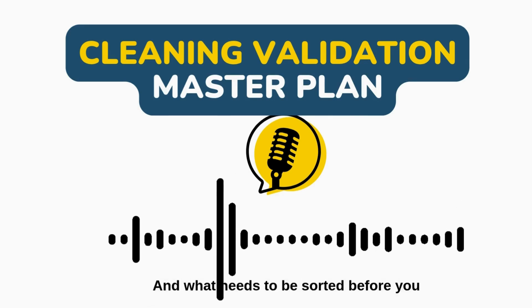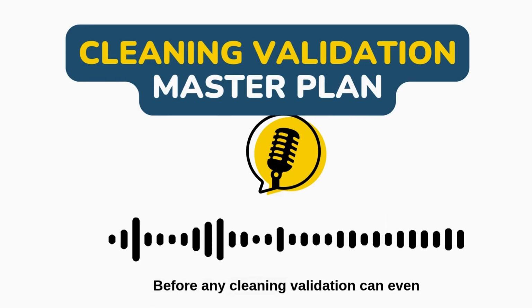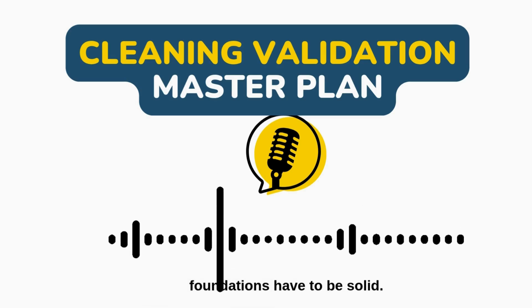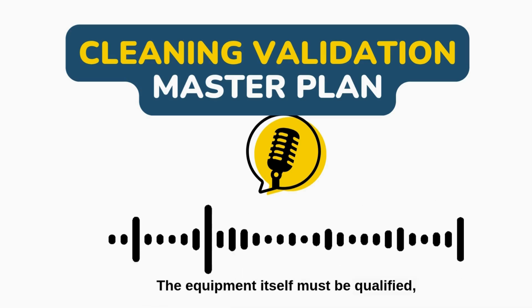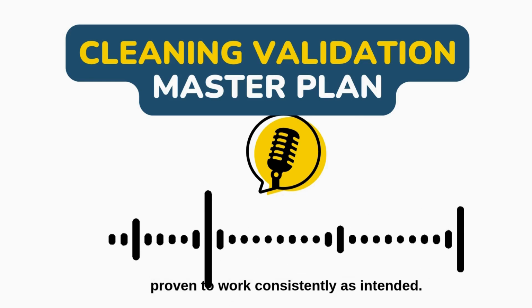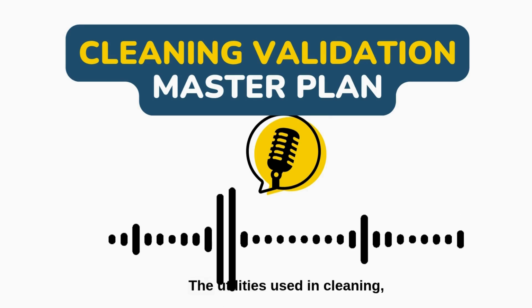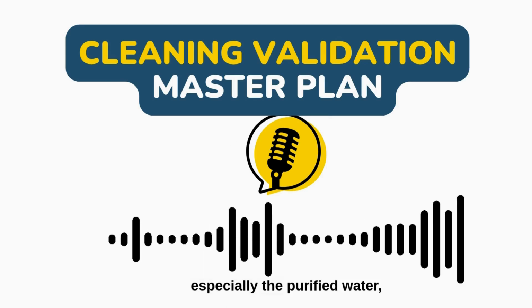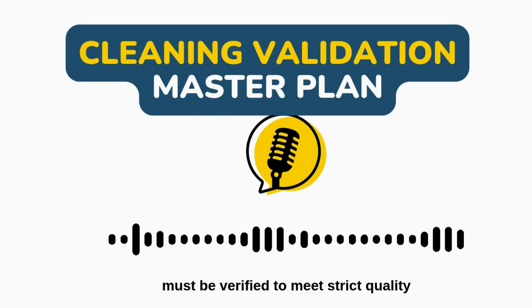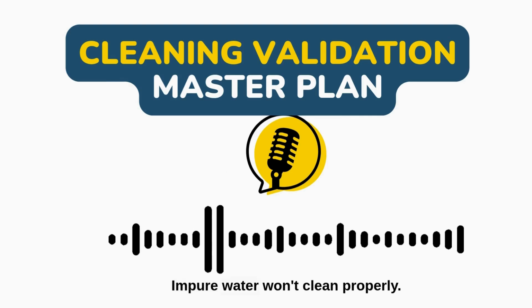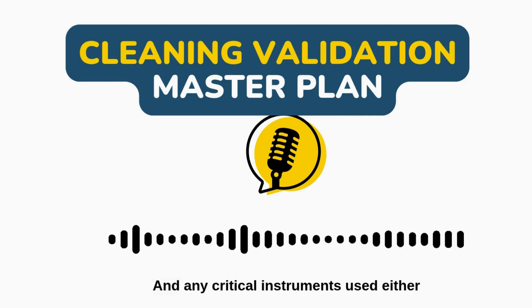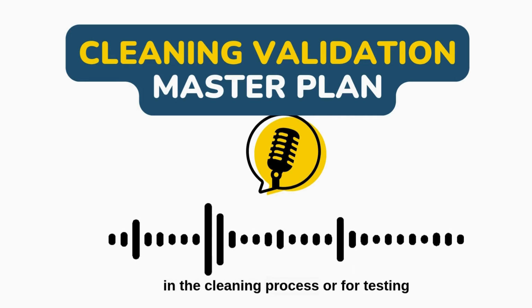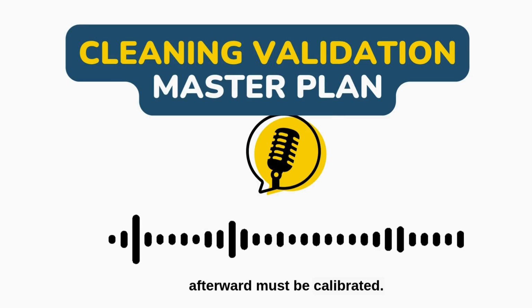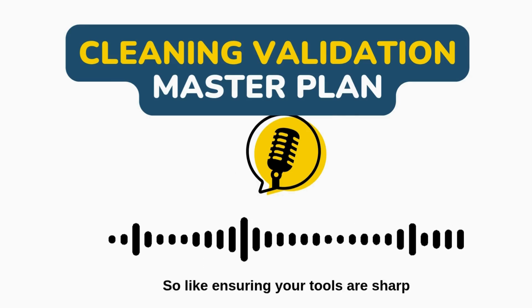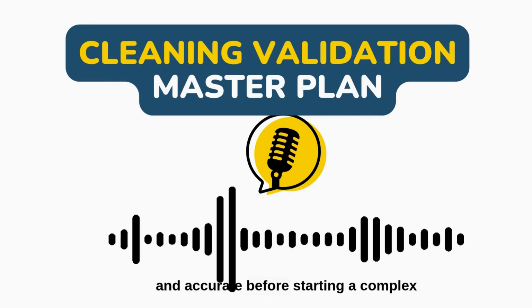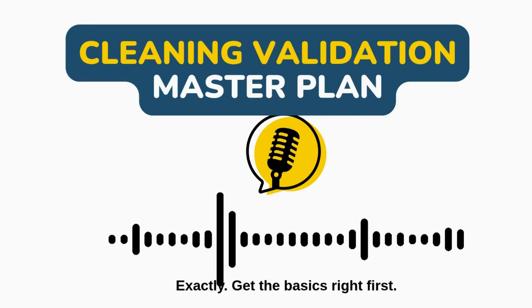And what needs to be sorted before you can even start validating it? Before any cleaning validation can begin, several foundations have to be solid. The equipment itself must be qualified, proven to work consistently as intended, checked and certified. The utilities used in cleaning, especially the purified water, must be verified to meet strict quality standards. Impure water won't clean properly. And any critical instruments used in the cleaning process or for testing afterward must be calibrated. Accurate measurements are essential. So, like ensuring your tools are sharp and accurate before starting a complex job. Exactly. Get the basics right first.